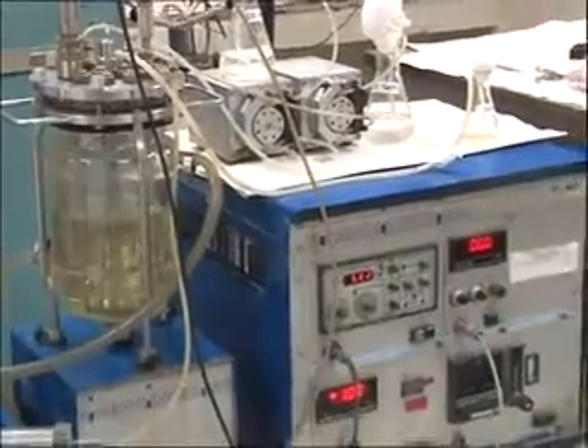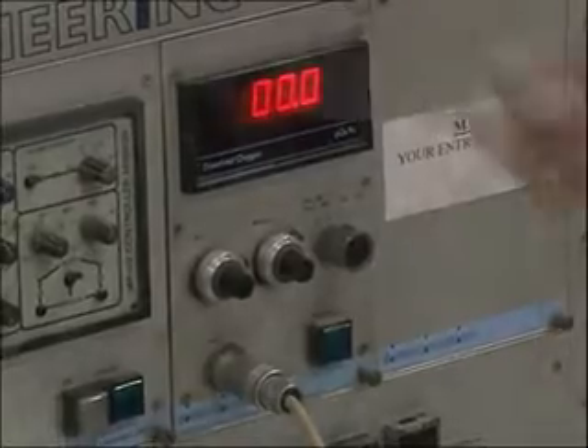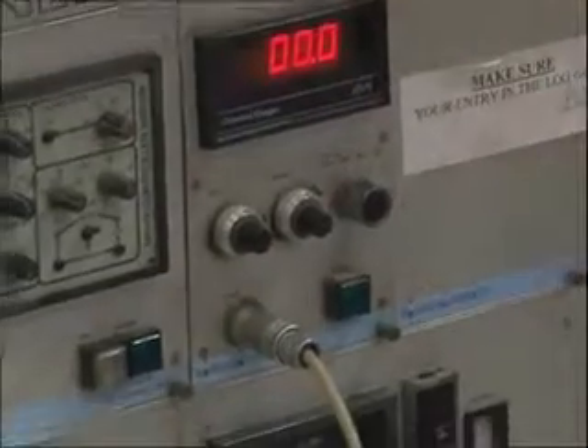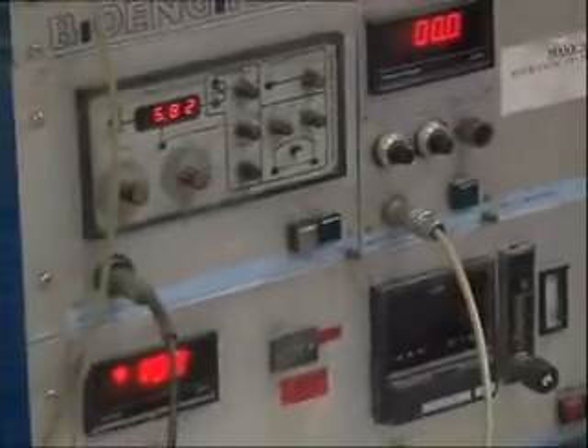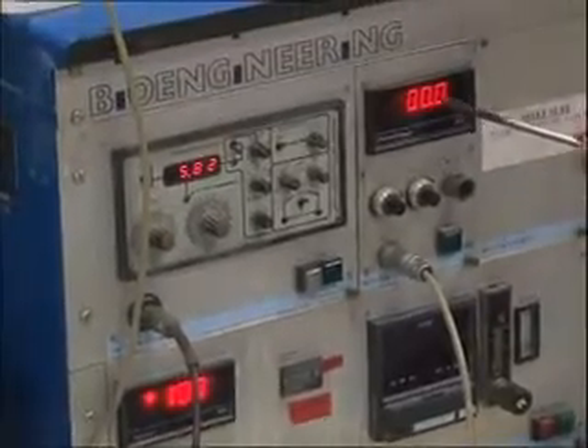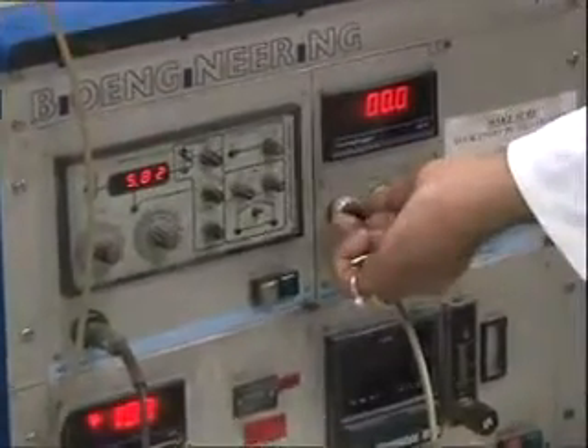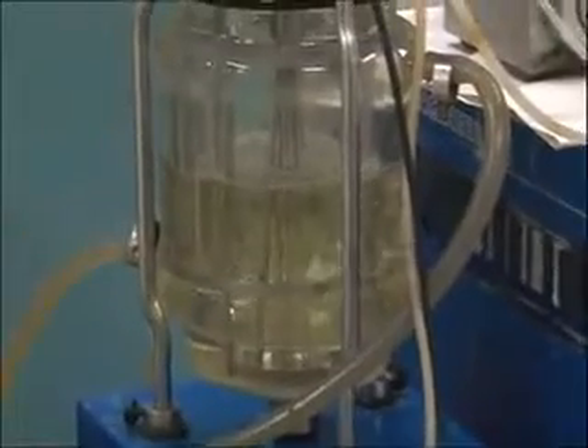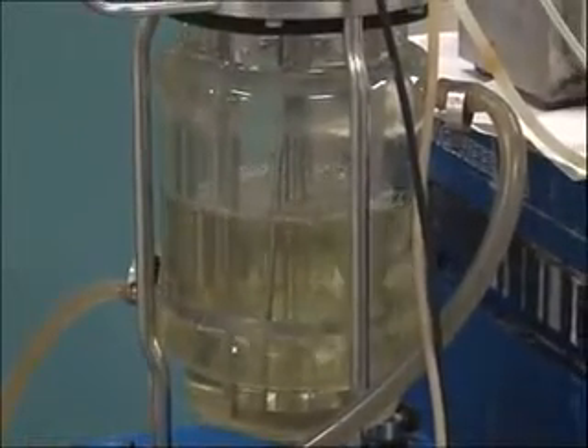So now whatever is the pH, it will be sensed by the controller, and appropriately acid or alkali will be added. In order to calibrate the dissolved oxygen, we purge the nitrogen in this, and we set the instrument to 0, and we basically measure the oxygen dissolved in the fermentation broth. Since we are purging nitrogen, it should read 0. If it is not reading 0, we just adjust it by the zero knob and make it 0 and lock it over here.